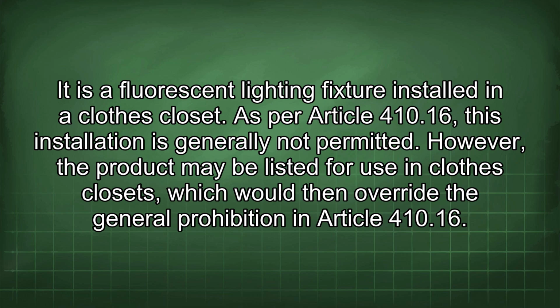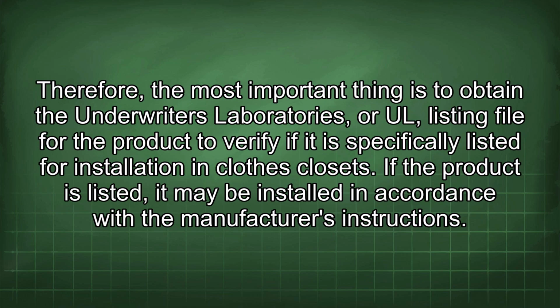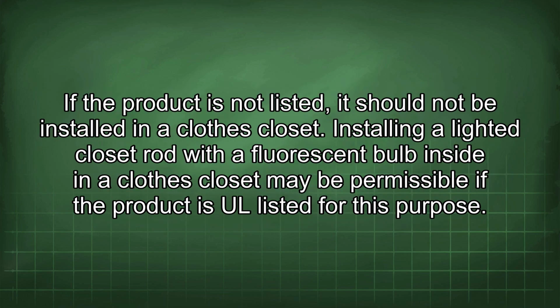However, the product may be listed for use in clothes closets, which would then override the general prohibition in Article 410.16. Therefore, the most important thing is to obtain the Underwriters Laboratories, or UL, listing file for the product to verify if it is specifically listed for installation in clothes closets. If the product is listed, it may be installed in accordance with the manufacturer's instructions. If the product is not listed, it should not be installed in a closed closet.